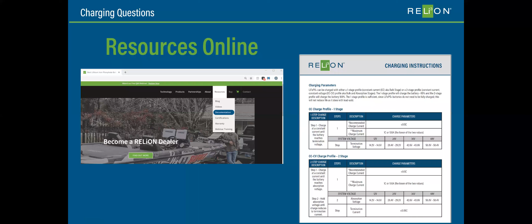Question: RELiON specs say 14 to 14.6 for bulk charging, 13.8 float. How much deviation from these figures is acceptable in charging? Recall from the 101 webinar, one of the strengths of lithium batteries is they can function in a partial state of charge, and they have protection against overcharging via an internal BMS. So there's a large deviation you can have. Ideally you charge in the 14 to 14.6 volt range to get 100% charged, and if you float, make sure you're balanced - that's optimal.